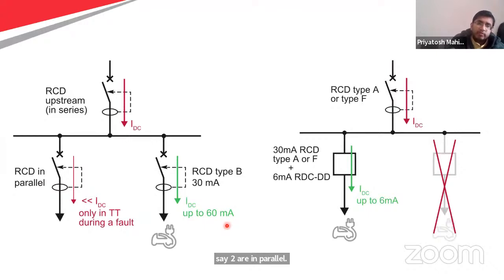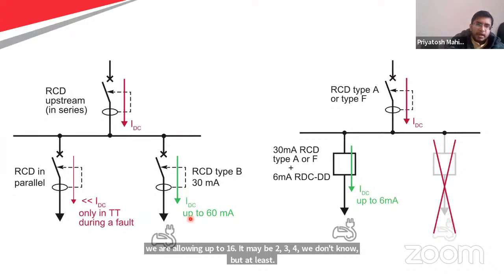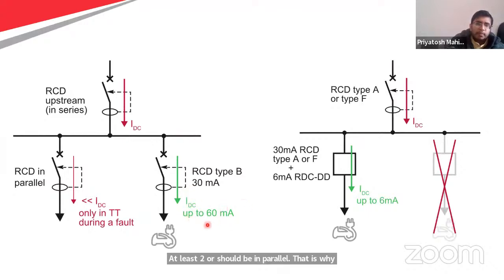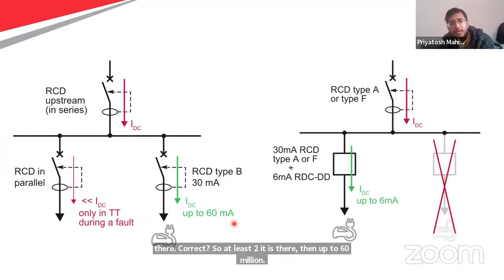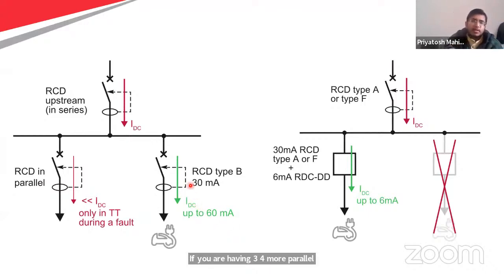It may be 2, 3, or 4, we don't know, but at least two should be in parallel. That is why I have written up to 60 milliamp. Parallel means at least two should be there, correct? So at least two it is there, then up to 60 milliamp. If you are having 3 or 4 more parallel connections, then you have to make more number of RCDs, correct, to make healthy operations.